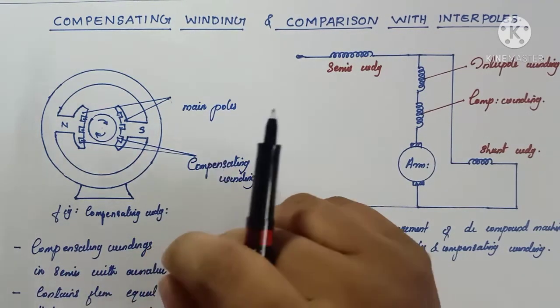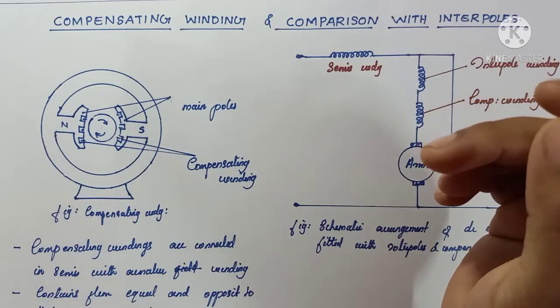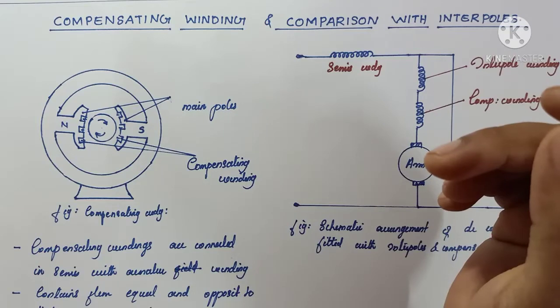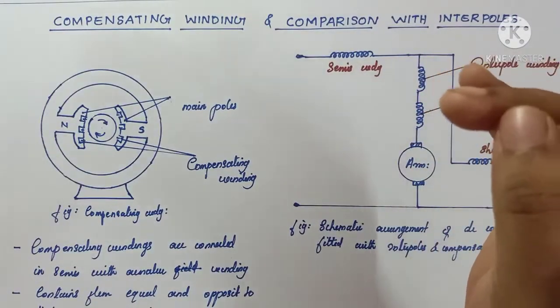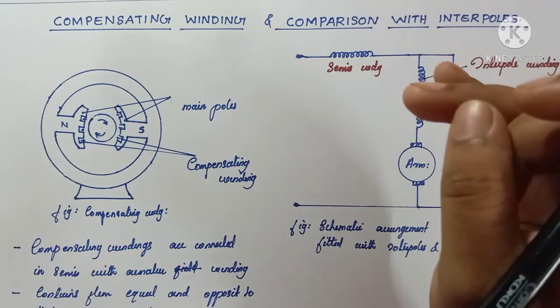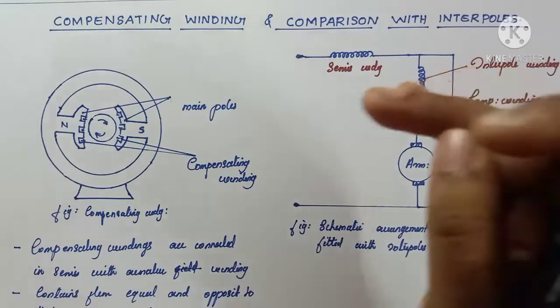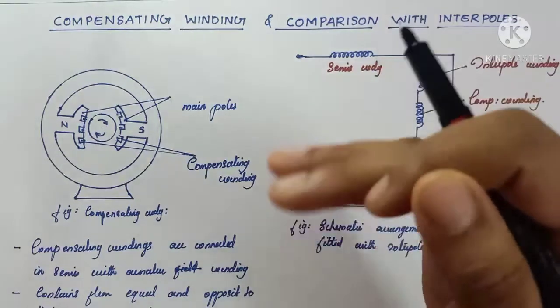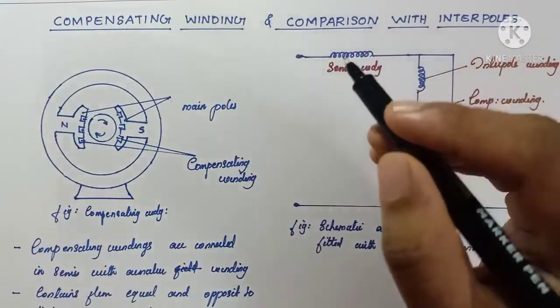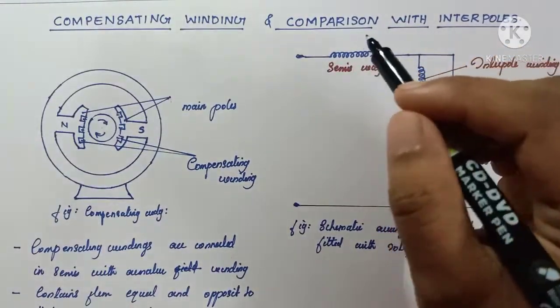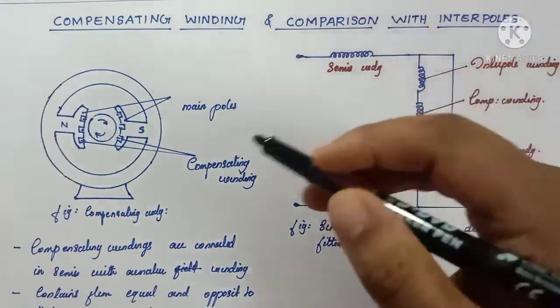Based on these discussions, we can conclude that commutation for DC machines can be improved by three methods. The first method is to use high-resistance carbon brushes instead of low-resistance copper brushes. The second method is the EMF or MMF method, which can be implemented by brush shifting or by using interpoles — the reactance voltage, which is the major cause of poor commutation, can be neutralized by interpoles. Brush shifting is not in practical use. The third method is the use of compensating windings.